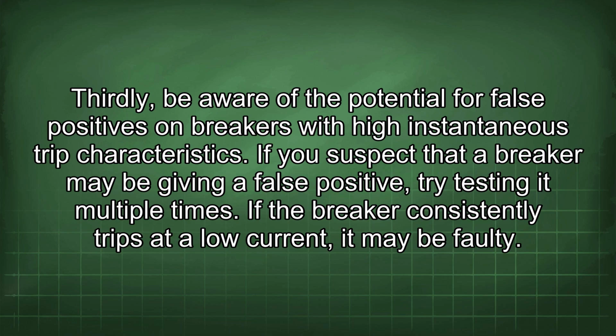Thirdly, be aware of the potential for false positives on breakers with high instantaneous trip characteristics. If you suspect that a breaker may be giving a false positive, try testing it multiple times. If the breaker consistently trips at a low current, it may be faulty.